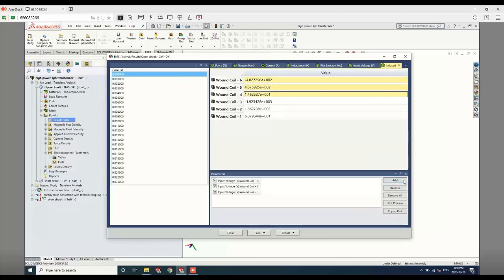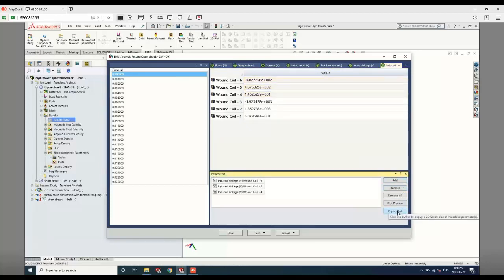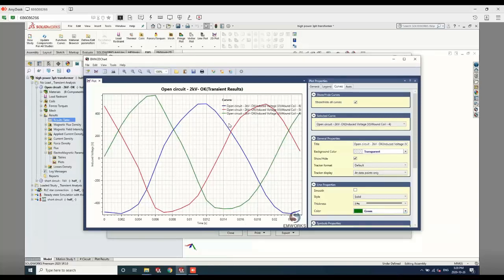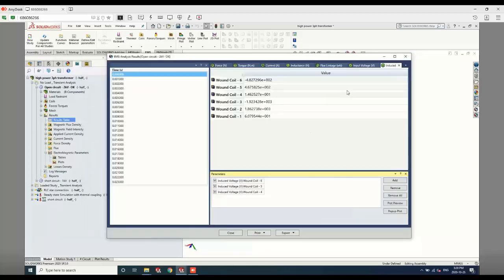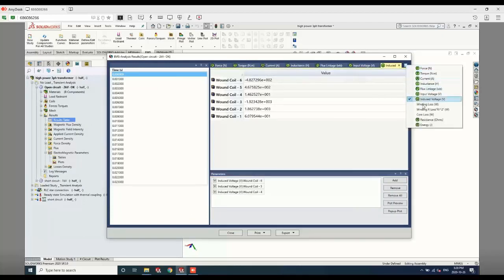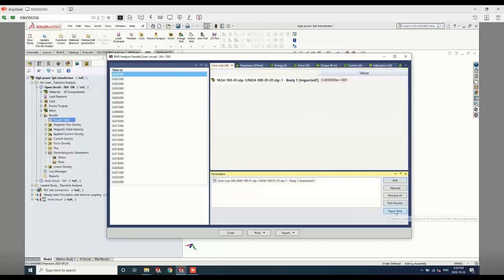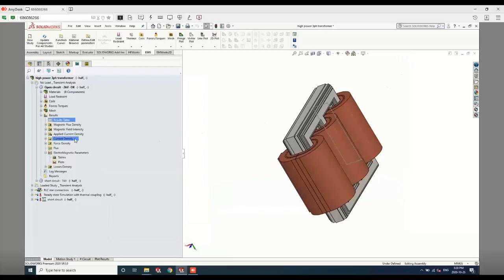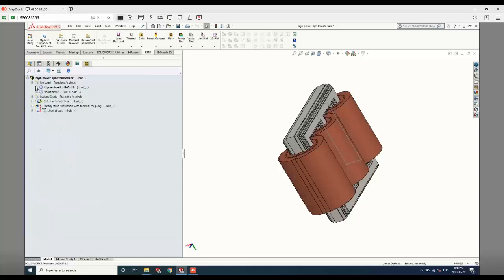You can see the secondary voltage is approximately 400-500 volts, confirming this is a step-down transformer. You can view other results such as current, inductance, core loss, and more. So in terms of electrical and electromagnetic behavior, you have access to many different quantities. Transient analysis is a useful first approach to analyze different electromagnetic behaviors. You also have open circuit and short circuit options available, and you can couple the transformer to an external circuit.